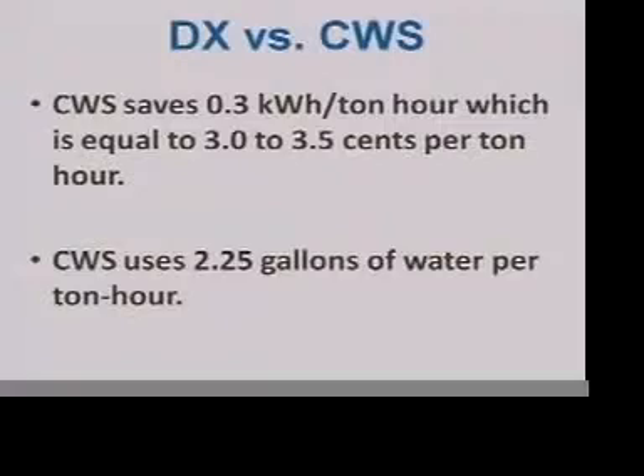And that just keeps on going. I won't make you read this one, it's too small. But this gets back to, well, what is the breakdown? Let's use those old direct expansion systems, like your home air conditioner does, with that unit outside that blows hot air out, the heat from inside your building. The difference is equal to about 0.3 kilowatt hours per ton hour, maybe 0.35, somewhere like that. That's worth somewhere between 3.0 to 3.5 cents per ton hour that you save on electricity.